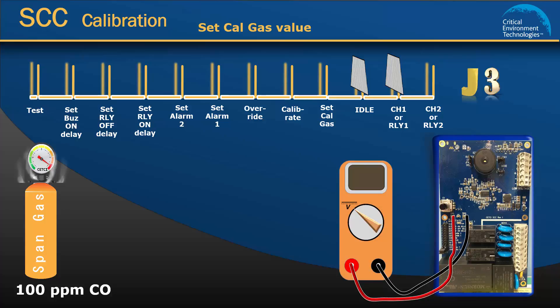To set the cal gas value, make sure one jumper is on channel 1 and move the idle jumper to set cal gas. Look at the voltmeter to confirm that the voltage is correct. In this exercise, it should show 2 volts. If it is not showing 2 volts, use the rotary encoder dial to adjust the number. To complete the set cal gas value procedure, move the cal gas jumper back to the idle position.